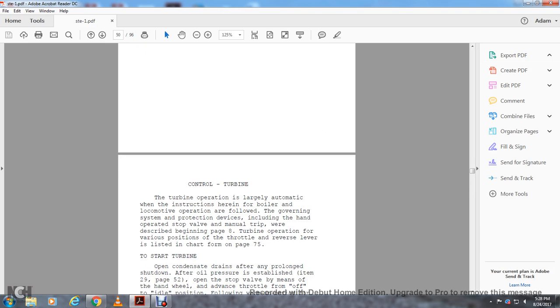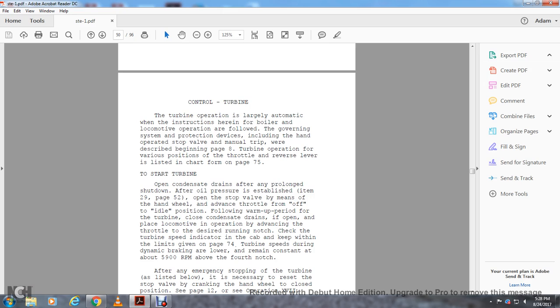Alright, control turbine. The turbine operates automatically if the instructions herein for the boiler locomotive operation are followed, with the governing system protective devices, including the hand operated stop valve and the manual trip, described in the beginning of page 8. The turbine operating valves operate with the various positions of the throttle and reverse lever, listed in the chart from page 75.